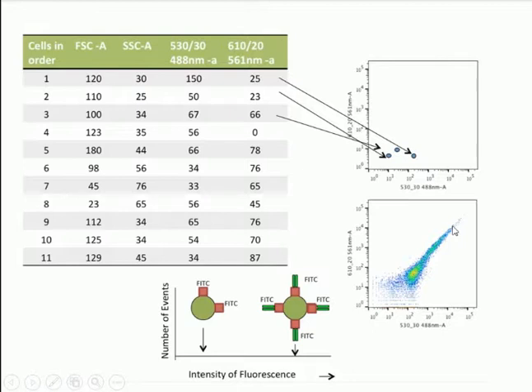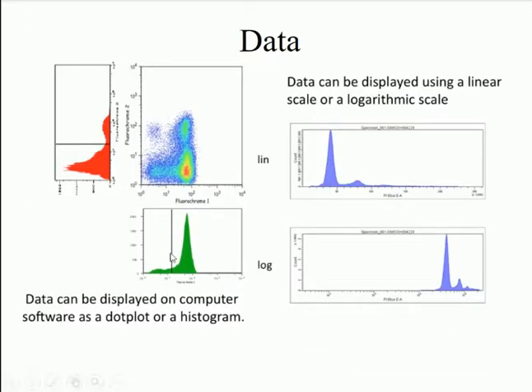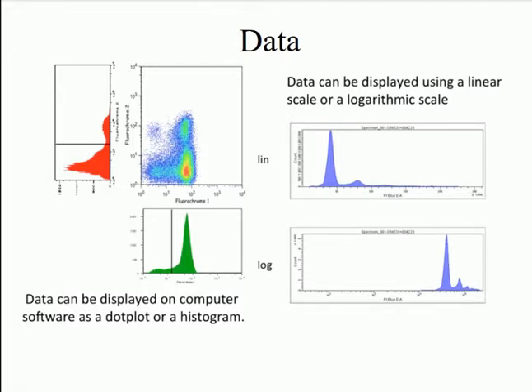Each cell with its attached fluorophore gives an intensity reading after laser excitation. The machine detects at that specific wavelength a specific reading for each single cell, and they accumulate in the graph. At the end you'll have millions of cells fitting in different areas, displayed using a dot plot on a logarithmic scale showing the number of cells emitting at a specific wavelength, and their forward and side scatter values.